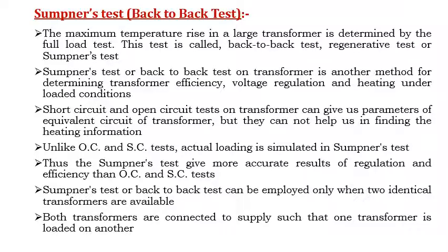This test is also called the back-to-back test or regenerative test. The Sumpner test gives the information regarding the maximum temperature rise in large transformers, which is to be determined by using the full load test. Sumpner test or back-to-back test is one more method for determining the transformer efficiency, voltage regulation and heating under loaded condition.